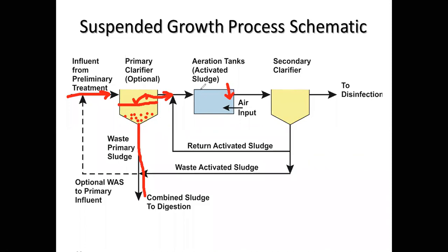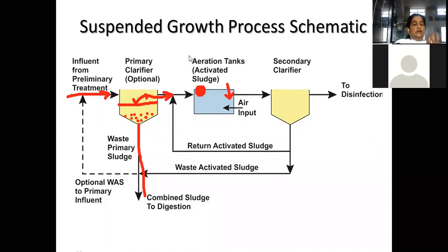Surface aerator in the sense, this tank will be full of the water which we want to treat, and the aerator can be arranged here, and it will rotate at a very high speed of 1000 RPM. It keeps on rotating. Part of the aerator, the blades, are arranged. I will play the video to make you understand. You can see the aerator is submerged into the water, so 50% of the part will be deep in the water, and 50% will be above the water.